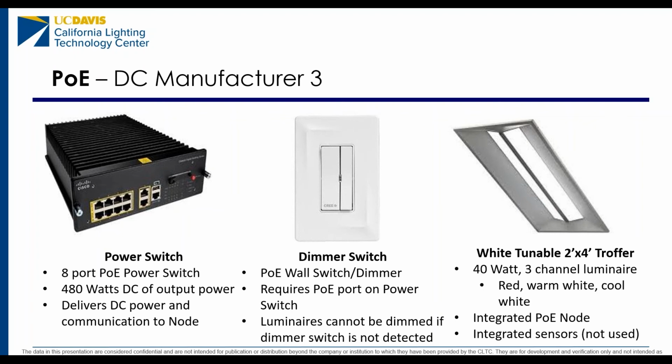These luminaires are, again, 40 watts. They're actually white tunable, and they have integrated sensors. For this study, we weren't interested in color tuning or in the sensors. We just wanted the luminaire we could buy for the system that had the highest wattage. So this was the one. And here it's important to point out 2 main differences between the 2 PoE systems that we looked at that actually did impact the findings.